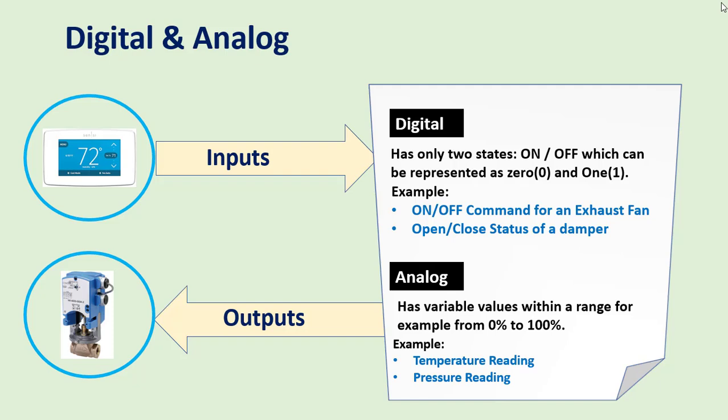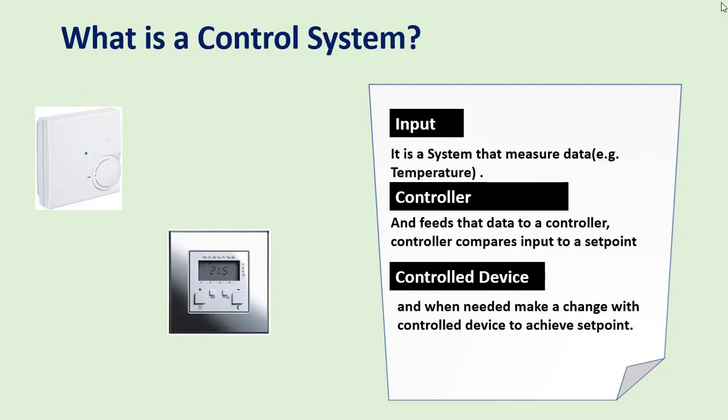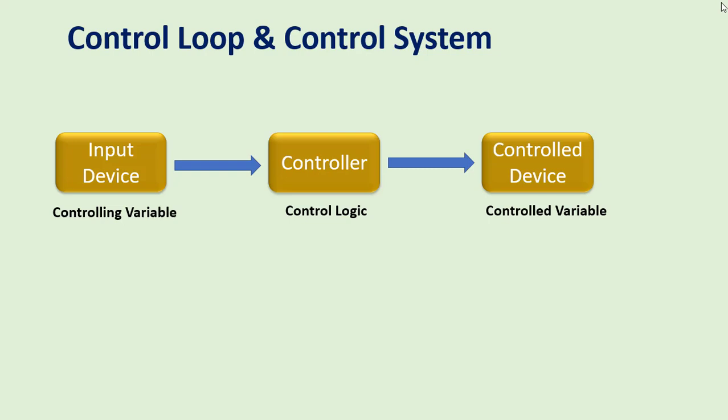To summarize, a control system measures data — for example temperature — and feeds that data to a controller. The controller compares the input to a setpoint, and when needed makes changes with the control device to achieve the setpoint. A simple control loop is defined as one input to a controller housing the control logic, which provides an output to a control device. A controller will typically contain a collection of control loops to manage a system.